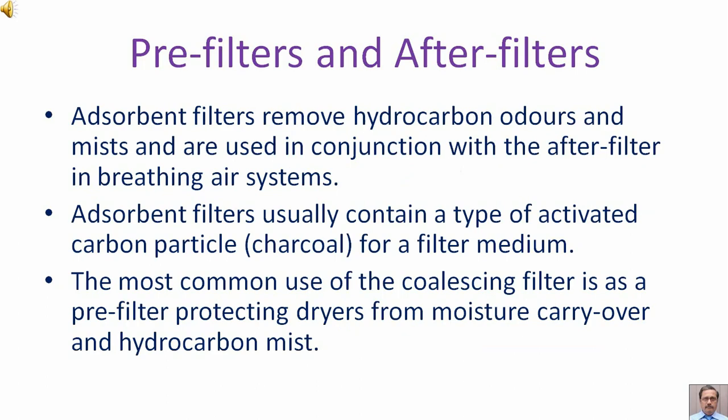Adsorbent filters remove hydrocarbon odors and mists and are used in conjunction with after-filters in breathing air systems. Adsorbent filters usually contain a type of activated carbon particle (charcoal) as the filter medium. The most common use of the coalescing filter is as a pre-filter, protecting dryers from moisture carry-over and hydrocarbon mist.